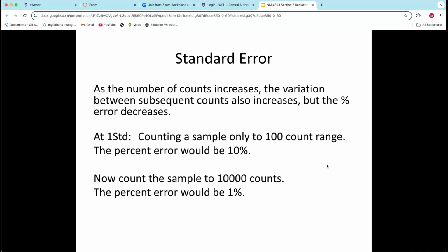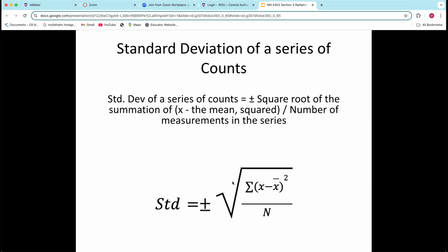And again, I just included the percent error thing here. What's interesting is that going from 100 counts to 10,000 counts, we brought our error from 10 to 1. But we don't even do 10,000 counts, right? You do like 500,000 counts or 750,000 counts. So if you did the math there, now you're down into the 0.0 whatever percentage range, right? So you bring your percentage of error way, way, way, way down, and you guarantee the accuracy of those images.